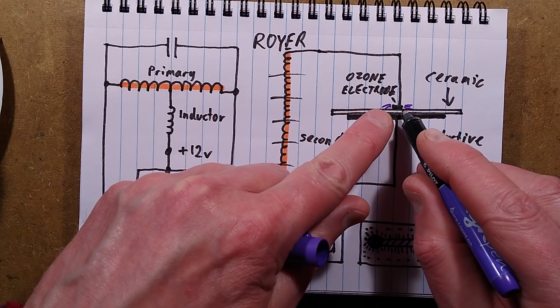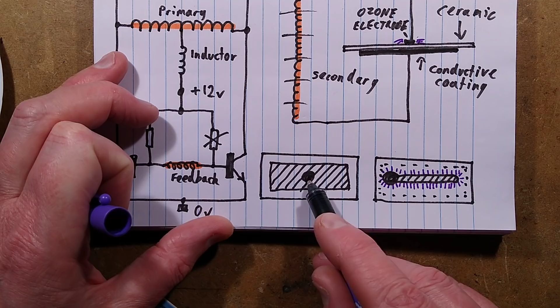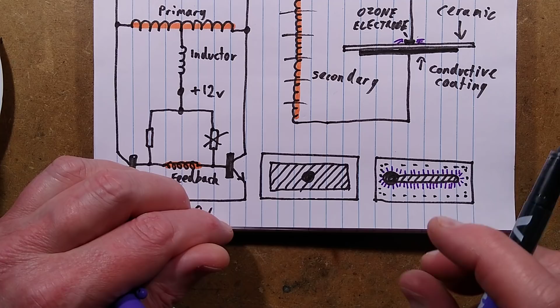Where that electrode isn't actually covering, you tend to get a fringe around the outside. So if we look at this drawing, on one side we've got the main electrode, which doesn't emit any ozone at all, and it's got a central solder connection. On the other side we've got the little central electrode, and sometimes that's one finger, sometimes two, sometimes a sort of figure eight. It depends how much area they want to create the corona discharge.